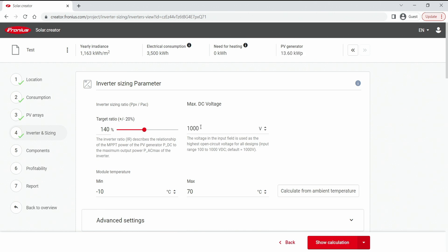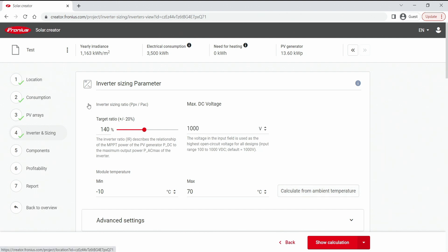The maximum DC voltage we can leave it to 1000 volt, that's the absolute maximum that we can work with. And the module temperature you can leave it as well on minus 10 and plus 70. Unless you want to work really in detail then you can hit the calculate from ambient temperature button. Then it will work with your location and the linked minimum and maximum temperatures that occur there.